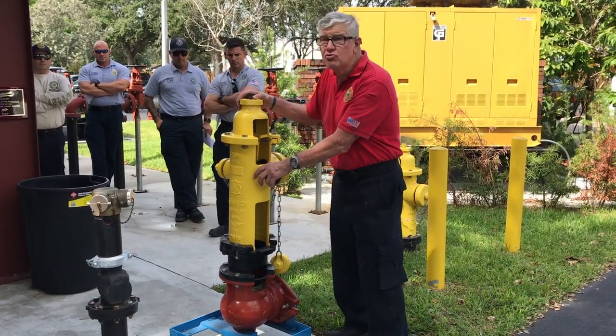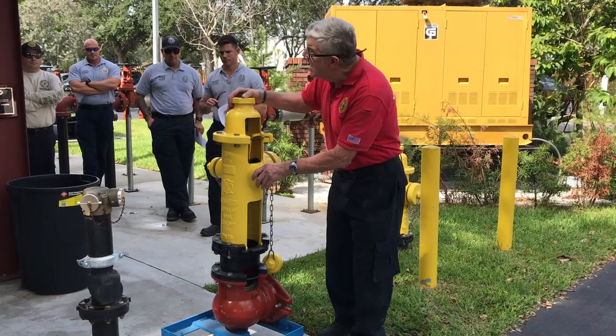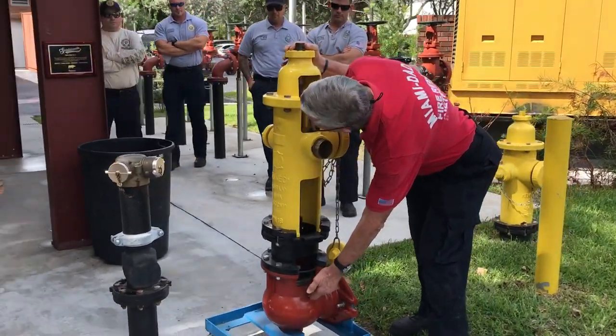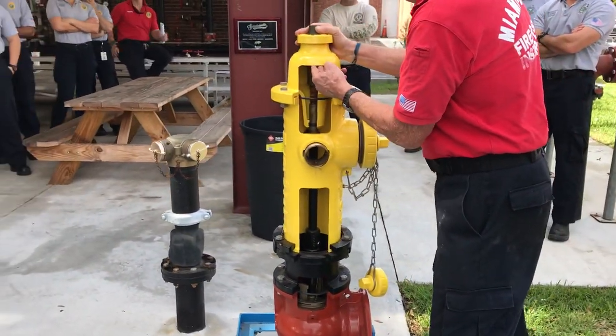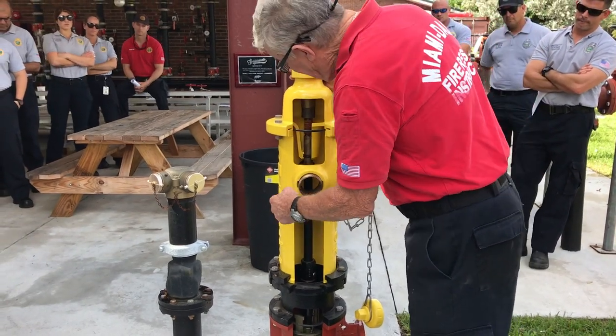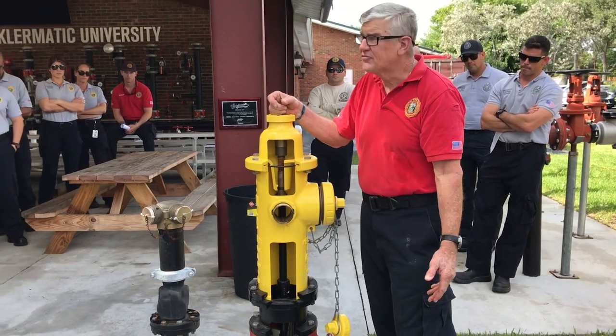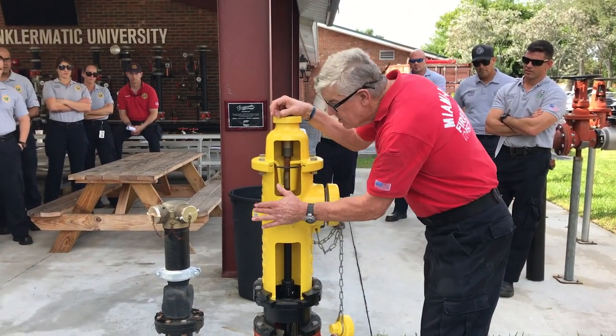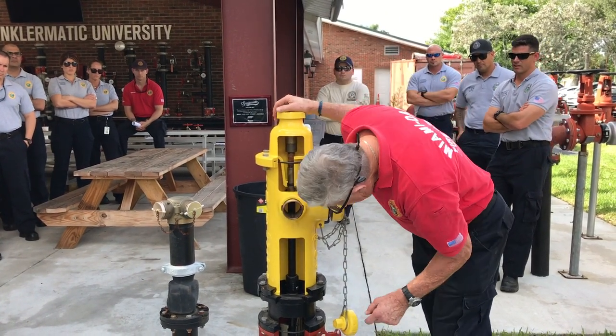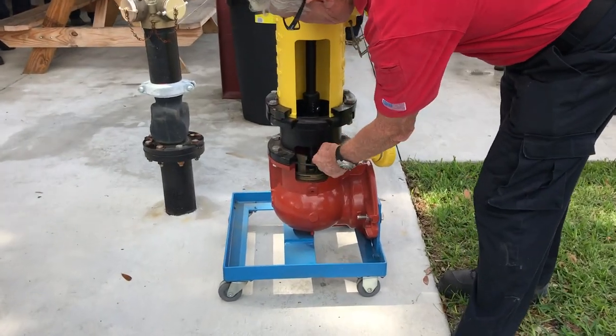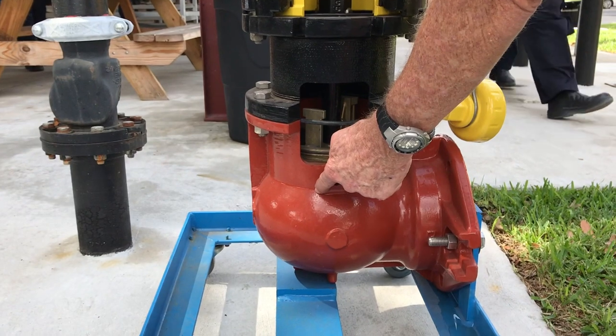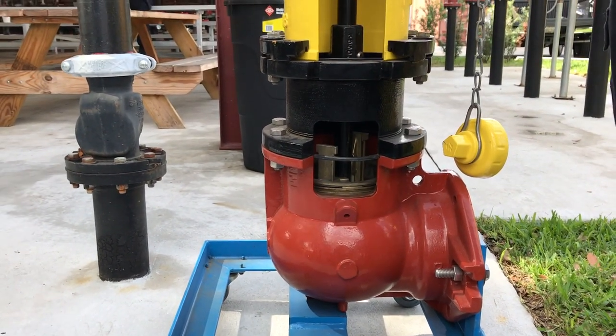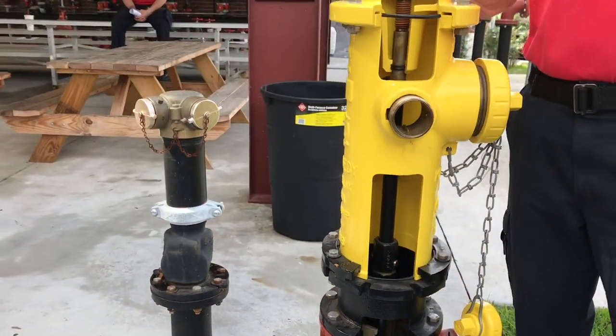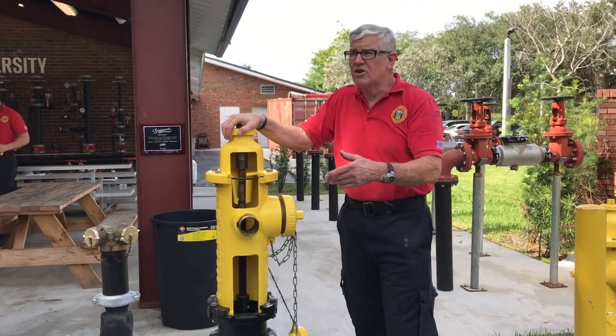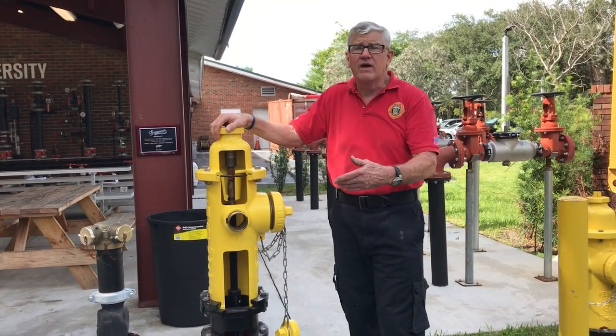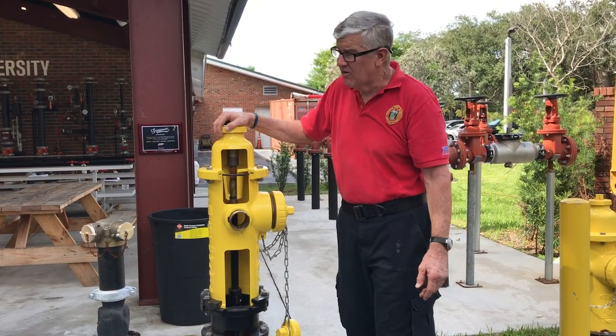Similarly, this is a dry barrel hydrant. When this hydrant is closed, all of this from the valve all the way up to the outlets and what we call the bonnet should be dry. As a firefighter up north, when I would fill a booster tank after a fire, muscle memory, we would close the hydrant, you put your hand over here to feel that the hydrant is draining. How would it drain? Right down here. When we open the hydrant, we close the drain. When we close the hydrant, we open the drain to allow the barrel to drain. If that doesn't happen, you'll have a frozen hydrant. And we know that is a huge problem in cities like Chicago and New York, where they have frozen hydrants. It's the nemesis of firefighters in the wintertime.